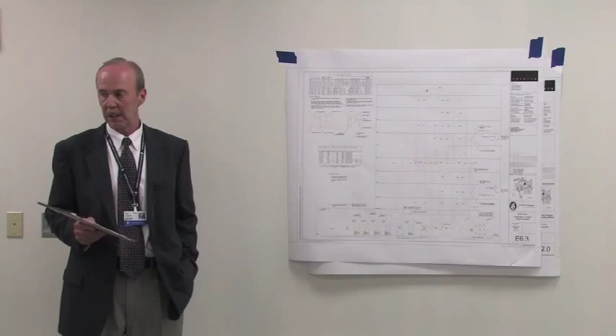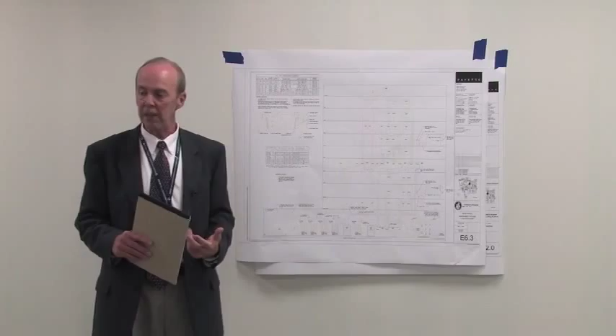Any other questions on any of the risers, any of the distribution? As I said, it's a pretty straightforward distribution system, there isn't a lot of complexity to it. You've got life safety on every third floor, you've got critical on every floor, on every patient floor. The critical and the normal feed your patient care areas for your dual sources. Your life safety will feed up and down on every other floor, so you're sharing that. That's similar to any other facilities.